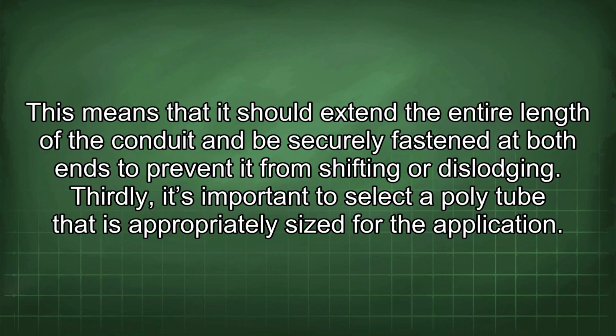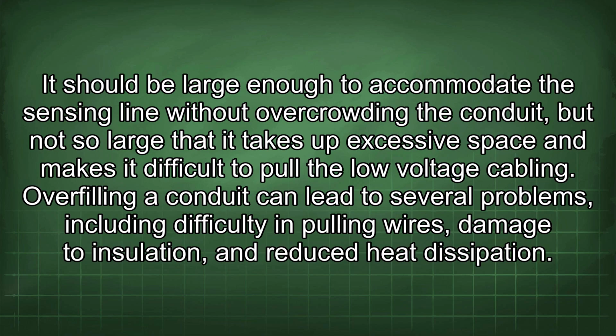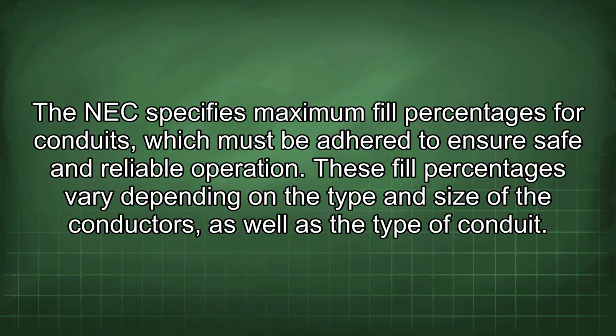Thirdly, it's important to select a polytube that is appropriately sized for the application. It should be large enough to accommodate the sensing line without overcrowding the conduit, but not so large that it takes up excessive space and makes it difficult to pull the low-voltage cabling. Overfilling a conduit can lead to several problems, including difficulty in pulling wires, damage to insulation, and reduced heat dissipation. The NEC specifies maximum fill percentages for conduits, which must be adhered to ensure safe and reliable operation. These fill percentages vary depending on the type and size of the conductors, as well as the type of conduit.